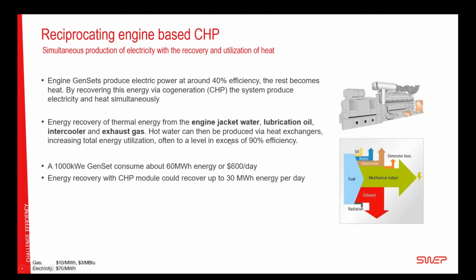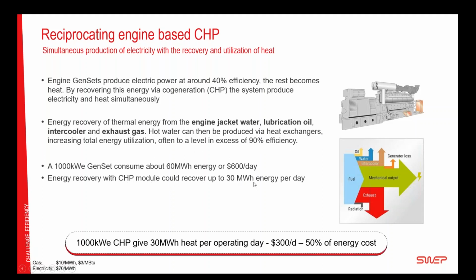To compare the genset to the combined heat and power, take a 1,000 kilowatt genset, meaning that it produces 1 megawatt of electricity. It consumes about 60 megawatt hours of fuel every day, and with the data we saw before, that's about $600 a day if we operate it on natural gas. If we just calculate the energy recovery, this part here, the CHP module, we will be able to recover about 30 megawatt hours per day, which is 50% of the energy cost that you put in. So you can save 50% of your energy running cost by going from a genset to a combined heat and power, if you can recover and redistribute that energy.